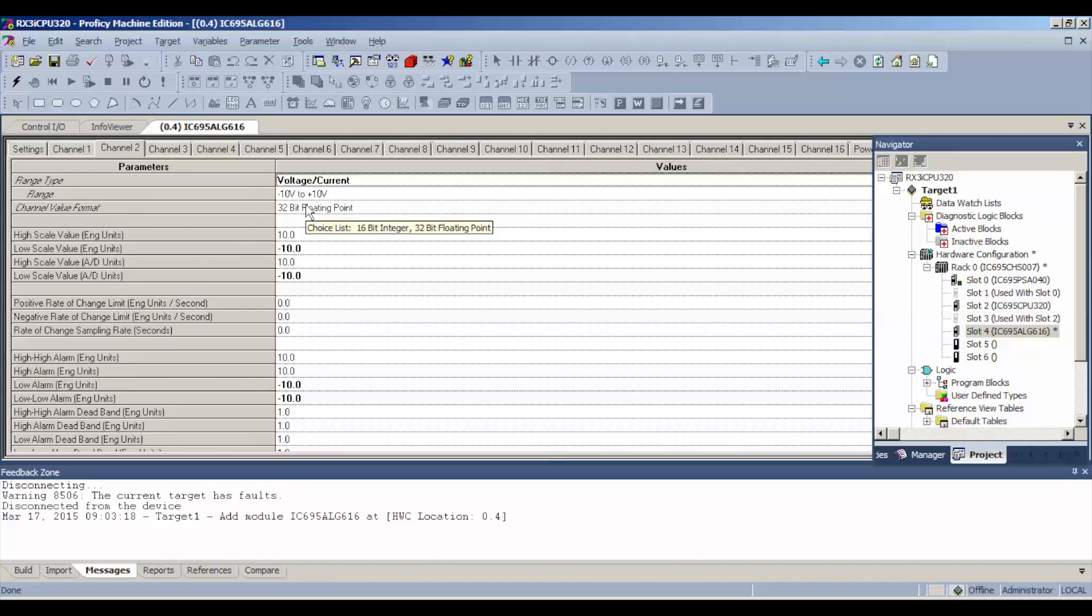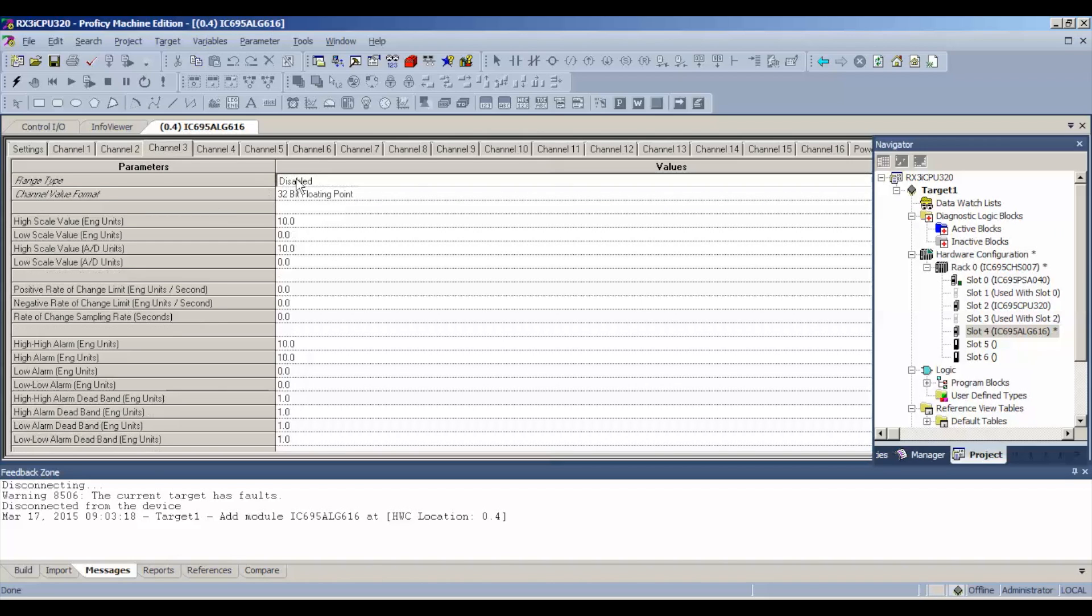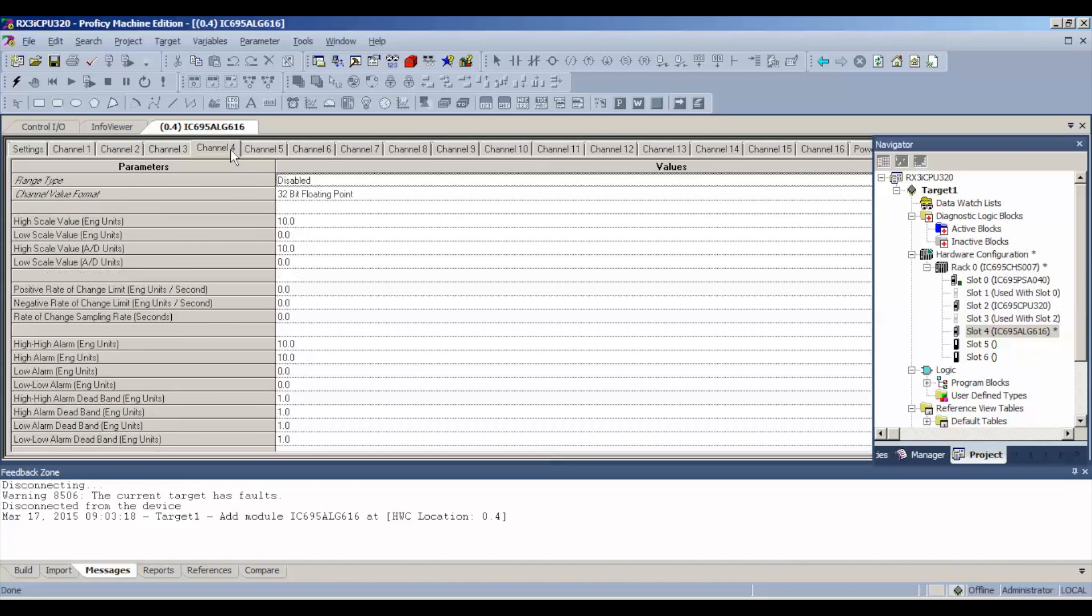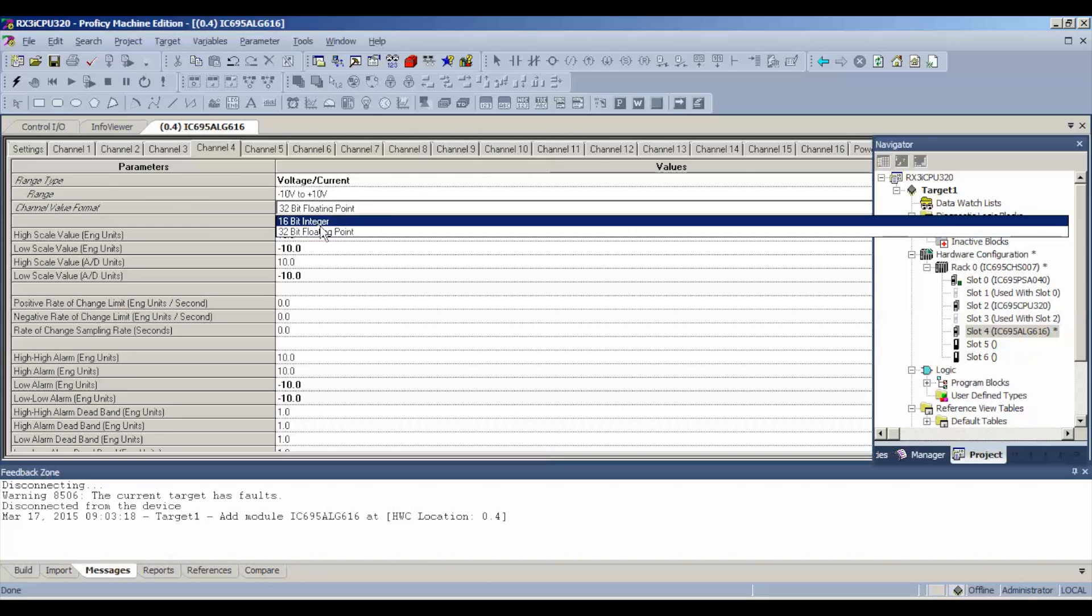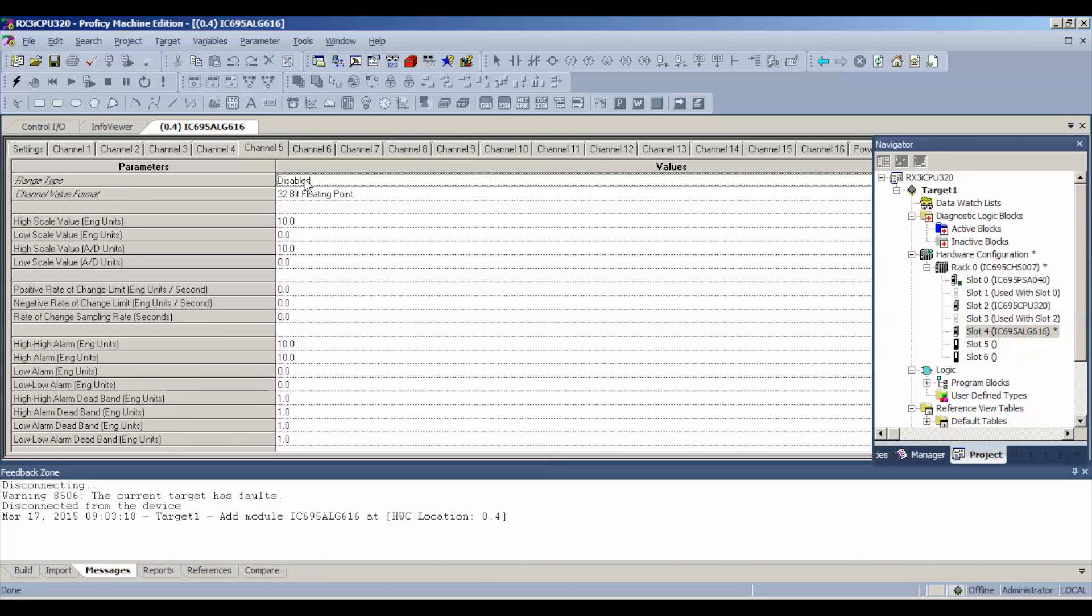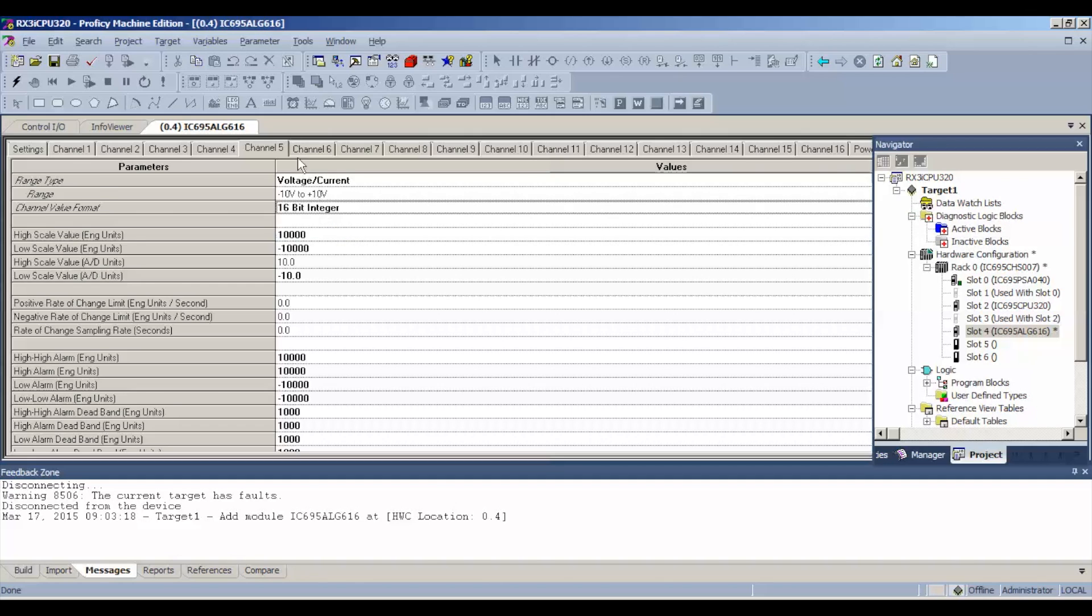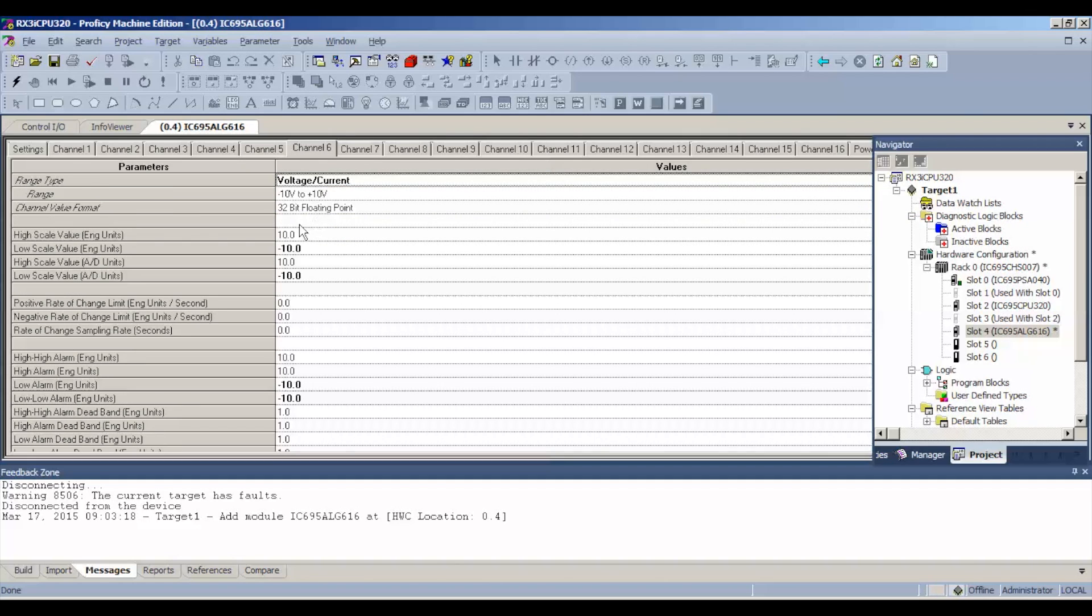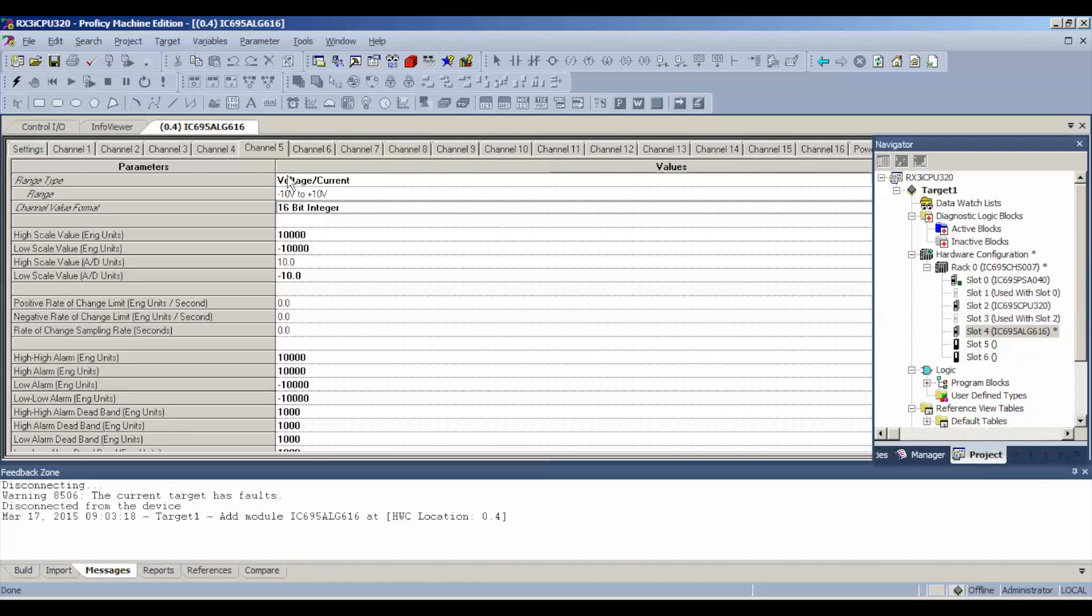We're going to select that and turn it on by hitting voltage current. The default range is negative 10 to positive 10 volts DC. We're going to go with the 10 volt DC, but we're going to change the channel format. Change the scaling to a 16-bit integer. Now we have negative 10 to positive 10 with values of 10,000 maximum or negative 10,000 minimum. We're going to go ahead with every channel and do that - enable the circuit, 10 volts DC, 16-bit integer. I'm just going to go through half a dozen channels doing this, and then we'll start a test. I got the first six channels. I recommend that you do all 16 channels, but this is just for example.